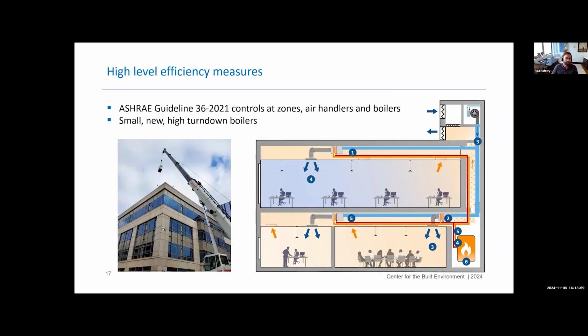At a high level, the measures that we did were we replaced the existing boilers as part of an end-of-life redundancy project, and we sized really small, new, high turn-down condensing equipment in replacing those large, oversized, non-condensing equipment. And then we also implemented best practice controls for the HVAC system following ASHRAE Guideline 36. And we did this everywhere, right? From the zones all the way up to the air handlers and the boilers.